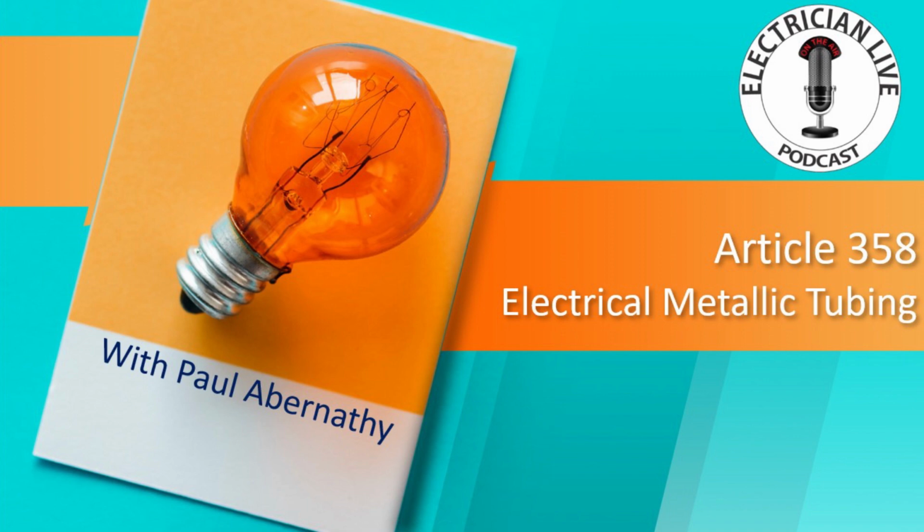Now, I get a lot of questions from people about the 2 conductors. Why is that at 31, but over 2 allows me to go up to 40? And the 31 has a lot to do with the jam effect and the way the conductors lay in the tube as they go around 90s and bend and things like that, and how they lay. Whereas usually when you have over 2, you come into what's called a cradle effect, and it just allows the conductors to stack. So a lot of that history has to do with those cross-sectional areas of fill, and that's where it kind of came from.